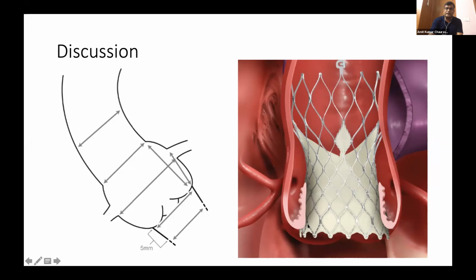Now, with the 34 millimeter valve, the diameter is 34 only at the top two struts, and then the rest of the struts behave just like a 29 millimeter valve. So if you're going to implant a 34 millimeter valve, it is better to implant slightly high, keeping the depth in mind that it should not exceed more than 5 millimeter. Otherwise, it tends to behave just like an annular valve.